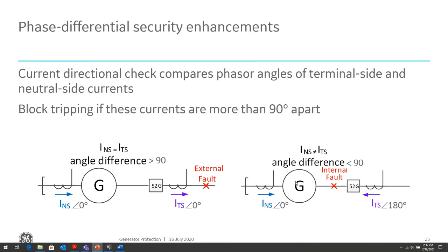But that's because of how we connect the CTs in our generator relay. So it will depend on how we connect our CTs. In this case, I'm showing the CTs on the generator neutral side are connected towards the generator neutral terminals, whereas the CT on the terminal side is connected away from the generator terminals. So that's what introduces that 180 degrees. So the connection of the CTs for generator differential is very important to get right.